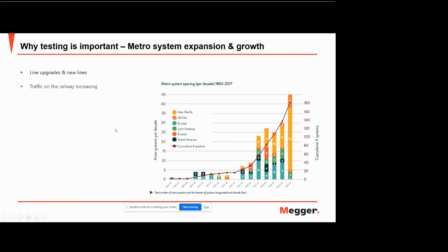What's also causing this? There's also increasing traffic on the lines to cope with the increasing demand with rail passengers. That also has an effect on the protection scheme that you have. So you then need to make sure that your protection scheme works accordingly to the increasing demand on that particular line. That may be a case of recalibrating some of your protection devices, and also to make sure that you have the correct protection in place for that increase in current demand on the lines.